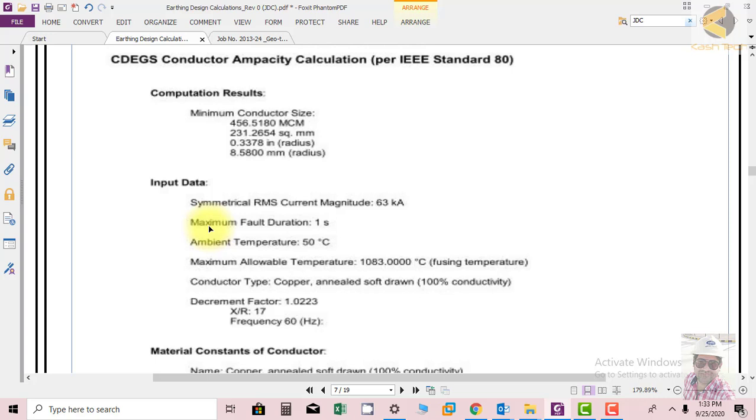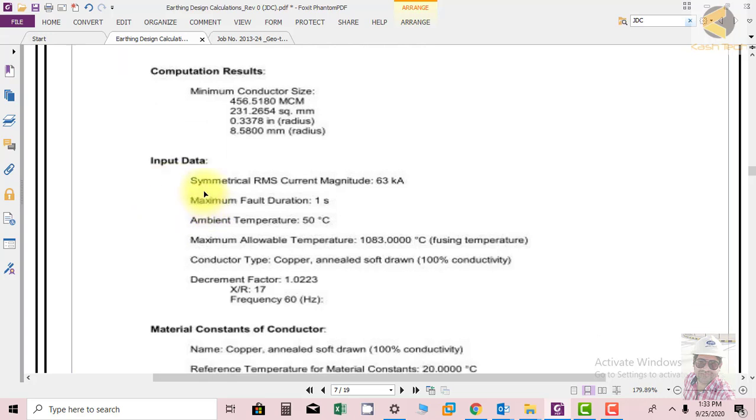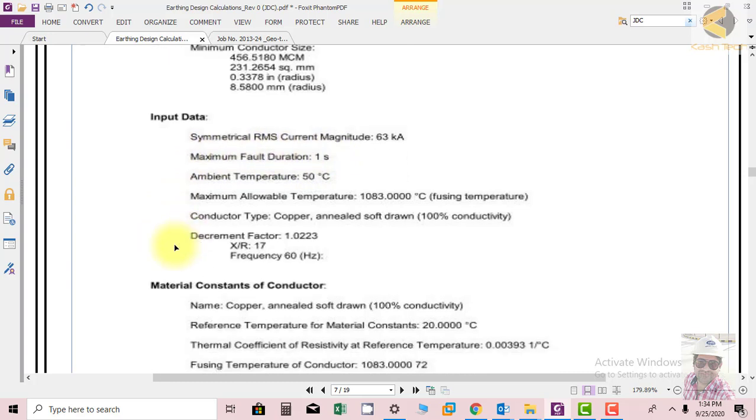In different parameters, sizes are given. Input data: it is showing the input data through the software. Symmetrical RMS current magnitude is 63 kiloamperes. Maximum fault duration is 1 second. This is the maximum fault duration. Actual fault duration by protection should be cleared in 0.5 seconds. With 50-100% margin we are using 1 second fault duration. Ambient temperature 50 degree centigrade.